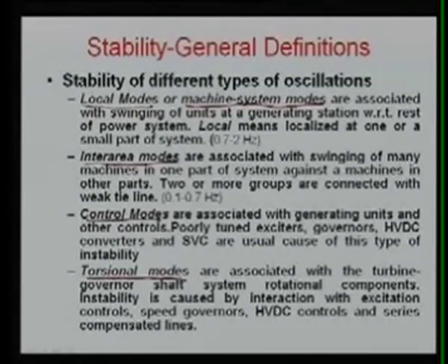Now let us see what is your local mode. The local modes are associated with the swinging of units at a generating station with respect to the rest of the power system. Local means localized at one or a small part of the system, and this frequency of oscillation is normally 0.7 to 2 hertz.